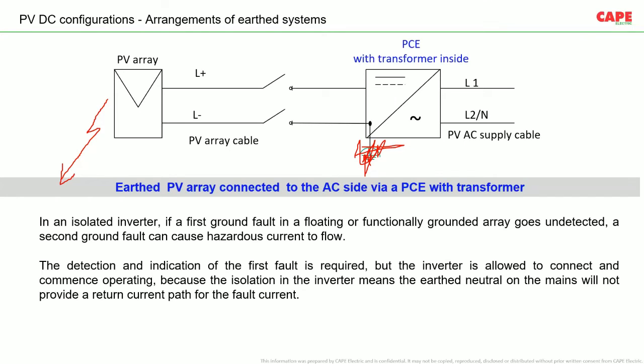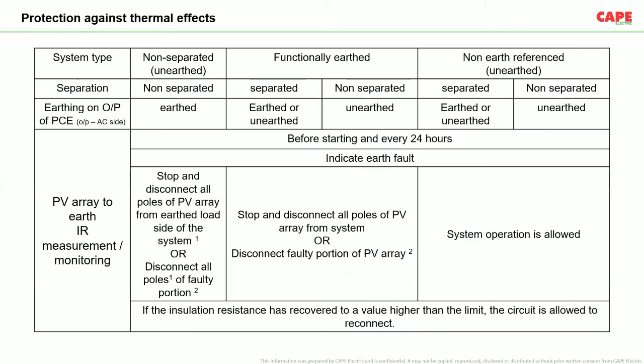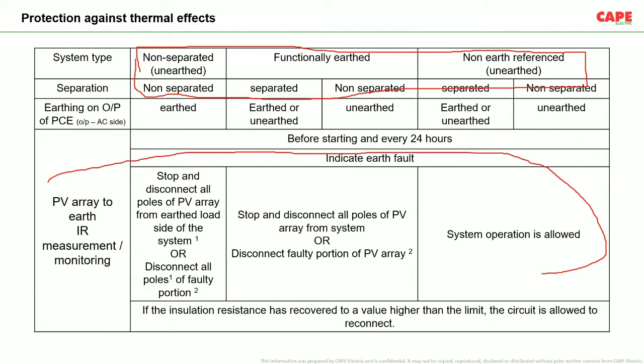Please note that the earth fault protection we are talking about is not protection from electric shock, but protection from fire. Protection from electric shock is achieved only by double insulation of the DC side. Now, protection against thermal effects. See, different kinds of systems. You can find this kind of table in the respective standard in almost all solar PV standards. You can see these configurations: non-separated, functionally earthed, non-earth referenced. Plus, the necessary safety measures are also included in the standard.